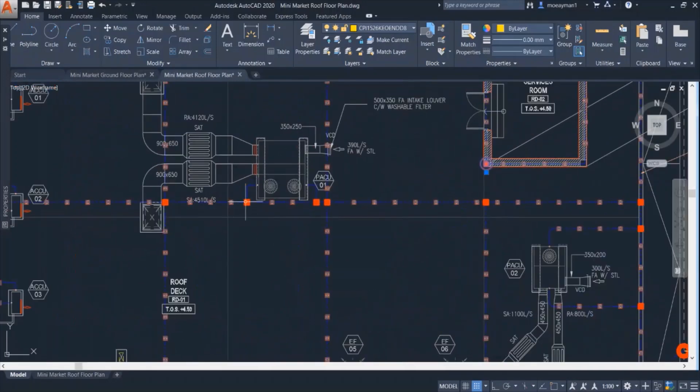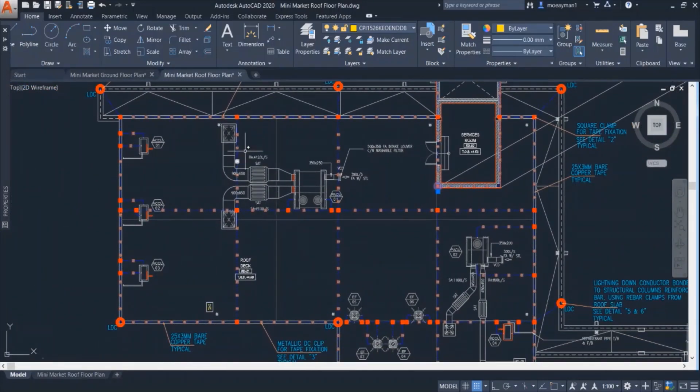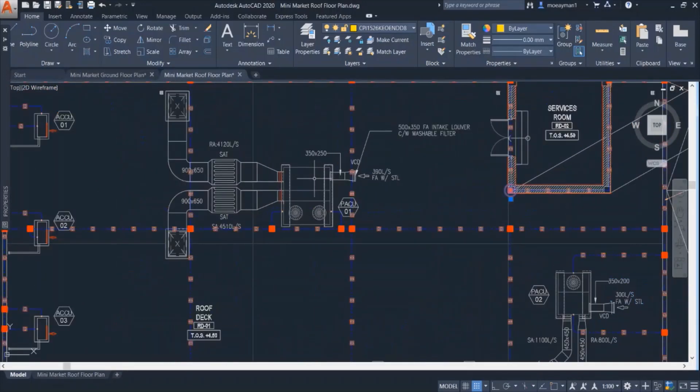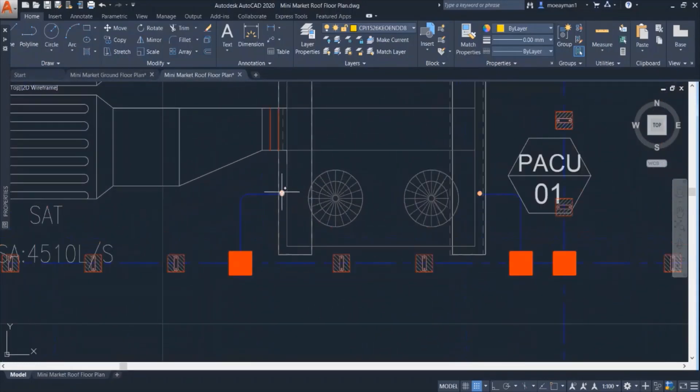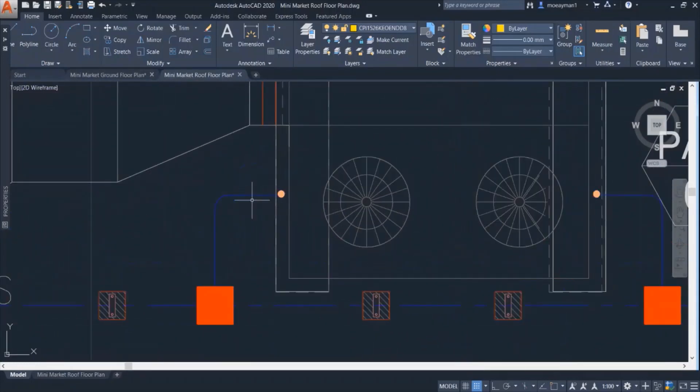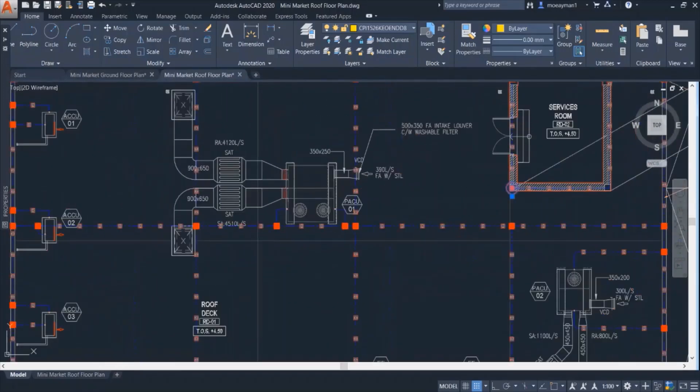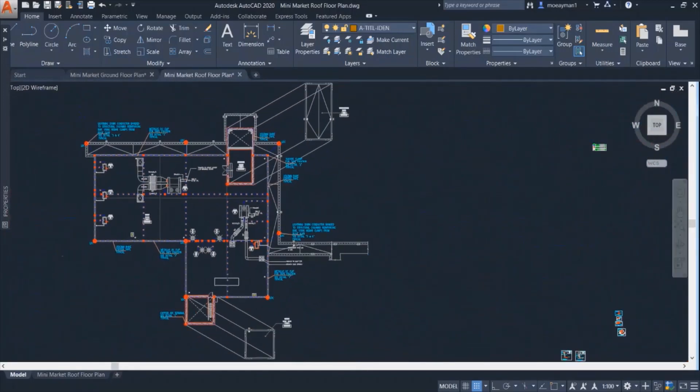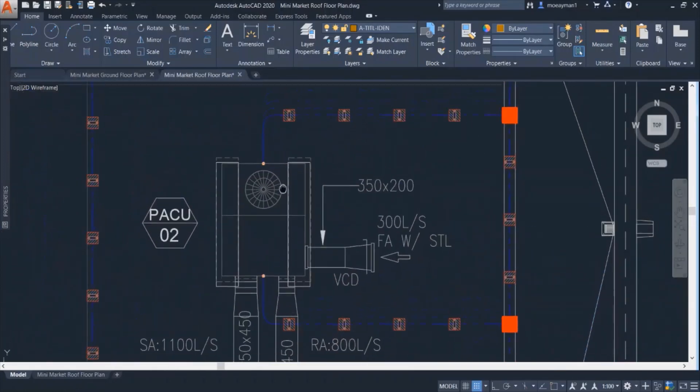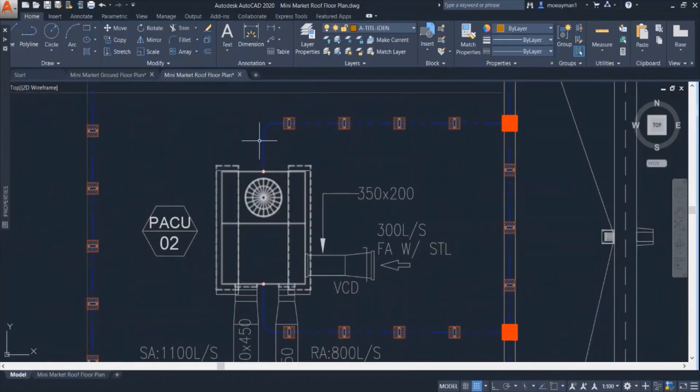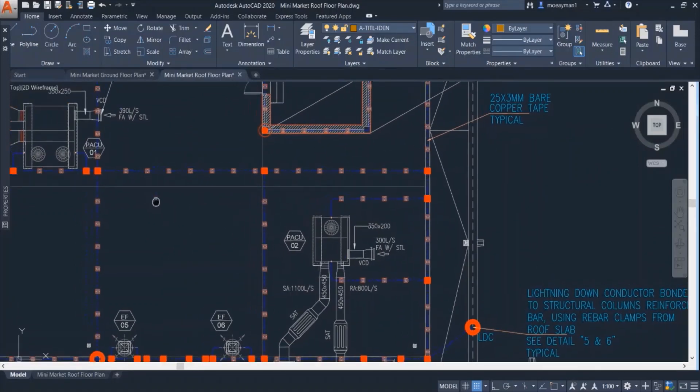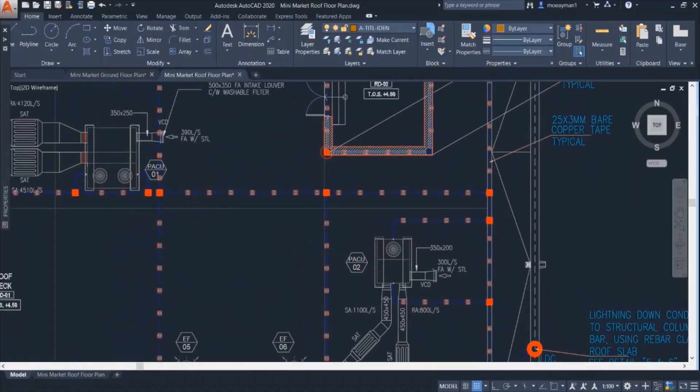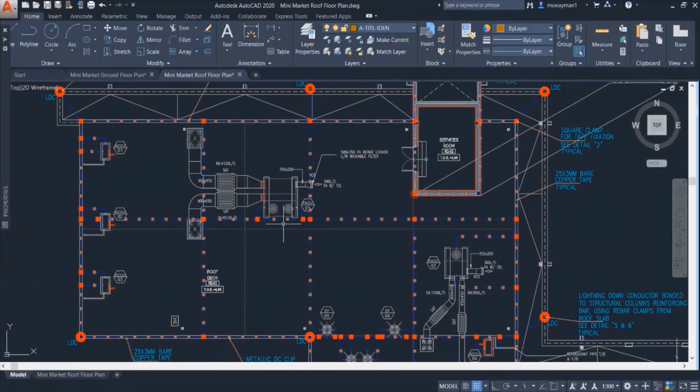So you will notice here that each of these outdoor unit is bonded to the lightning network. For example we can see that the outer case of this outdoor unit is bonded to the lightning network. Same like this outdoor unit it is bonded from both sides. This ensures the safety of this equipment and since these outdoor units are exposed to air. So we have to protect them against lightning by connecting them or bonding them to the lightning system.